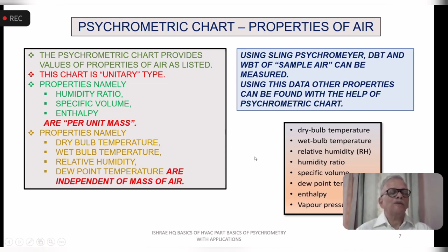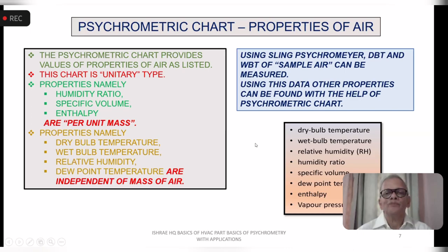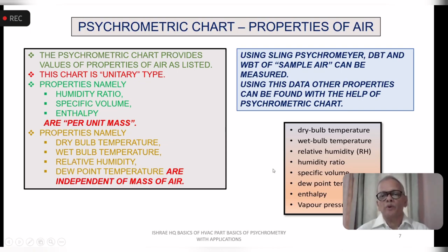Now, to get the properties of air, you would need a laboratory if you have to weigh the mass of the air. Suppose we have a room of 3 meters by 5 meters and 2 meters height. The volume is calculated, and to weigh that sample of air is practically impossible. And that's where you have this benefit: using a sling psychrometer, the dry bulb and wet bulb temperature will be measured, which is very easy. Simple instruments are used, and using these two parameters, we take them to the psychrometric chart and you get all the remaining properties, because that air sample is pinpointed with these two properties, and the rest of the properties are easily available or can be computed. So that's the beauty of the psychrometric chart, and that's the most helpful tool, I would say, in understanding the HVAC requirements.